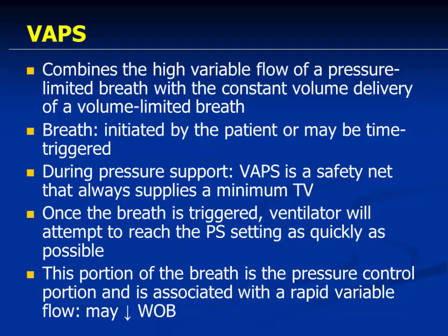Coming to volume assured pressure support, it combines the high variable flow of a pressure limited breath. So in a pressure limited breath, what happens? Flow is very variable, with a constant volume delivery of a volume limited breath. So it is trying to keep a constant volume and giving the variable flow of a pressure breath. The breath is initiated by the patient or maybe time triggered. So either the ventilator is giving the breath or the patient is taking the breath. It can happen in both phases.